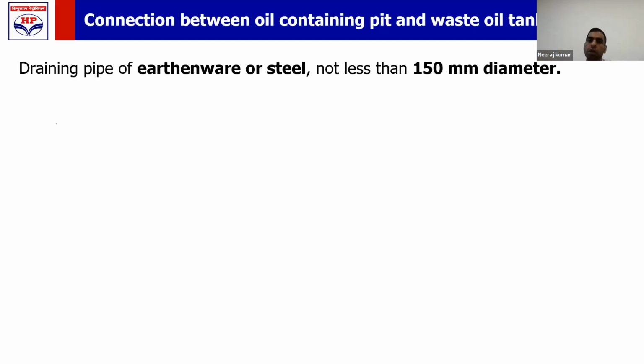हो सकता है. It is also possible that you have used one waste oil tank for many transformers. Refinery में it is very common. 4-5 ट्रांसफार्मर के लिए बीच में एक बड़ा सा वेस्ट ऑयल टैंक बना देते हैं. In that case or in any case, you should connect these waste oil tanks and your oil containing pit with a pipe. Now specifications of the pipe are specifically given in the standard. The diameter of these pipes shall be 150 mm or more. उससे कम का diameter नहीं चलेगा.